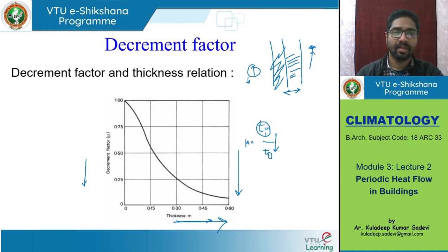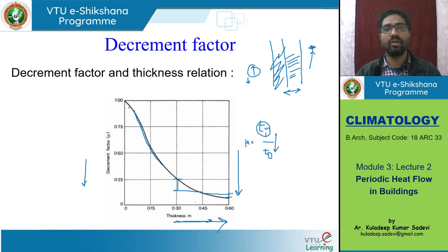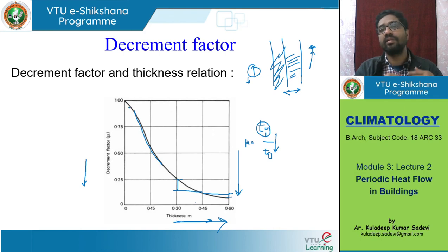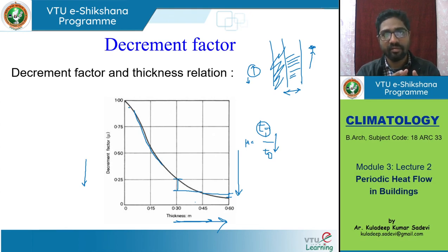Another important point: once we start adding up the thickness of the wall, the decrement factor reduces exponentially very quickly at first, but after some point — around 0.45 to 0.6 meters — the rate of change for each additional 0.15 meters is not that much. More thickness you keep adding, the effect on the decrement factor is not going to be as high. In the initial range from a thin wall to a much thicker wall, the decrement factor changes drastically, but if the wall is already very thick, adding more thickness doesn't give much change in decrement factor. The change is much higher at lower thicknesses.